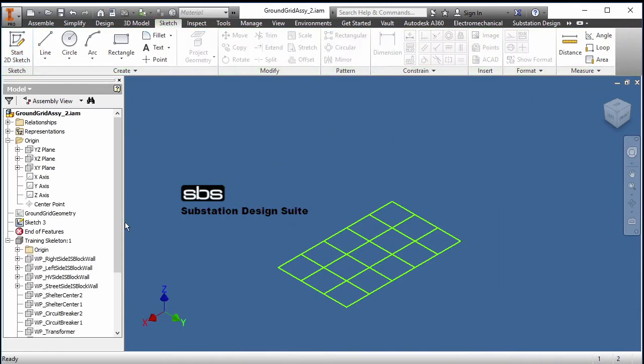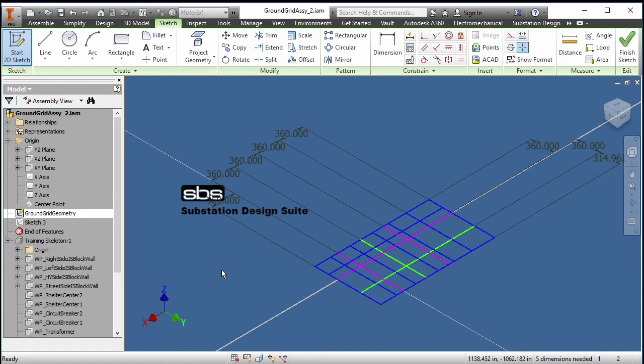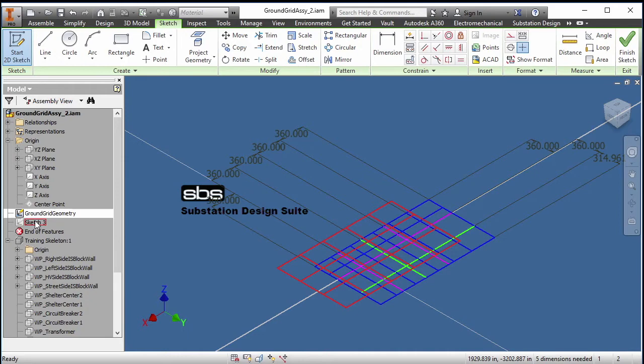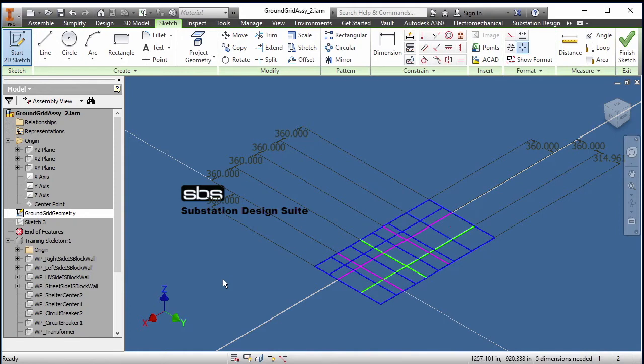In this case, what we're going to do is run our ground grid from geometry already built. Here's my ground grid — this was built using normal Inventor sketch tools. I have my skeletons for reference. What the ground grid tool does is look for blue lines to create a ground grid. In the AutoCAD sketch we had previously, we would have to change the color of the lines to blue. That's easily done — you right-click and go into properties. So here I have my ground grid sketch, and I will finish that sketch and make it visible.